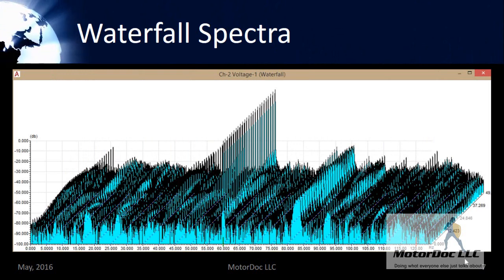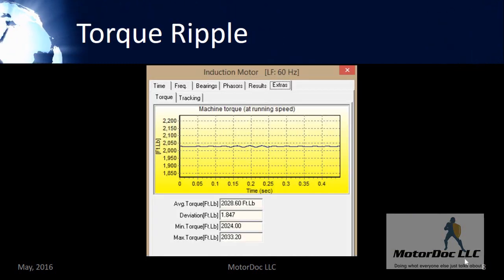When I'm starting to look at those wide bases, I would pull up a waterfall plot. That waterfall plot allows me to look at why I have a wide base. What other people may not realize is that a wind generator is a variable speed generator. When we're looking at variations in wind, you can see small changes in speed. Those small changes in speed carry all the way back to the generator, and we are looking at what's going on in the air gap.